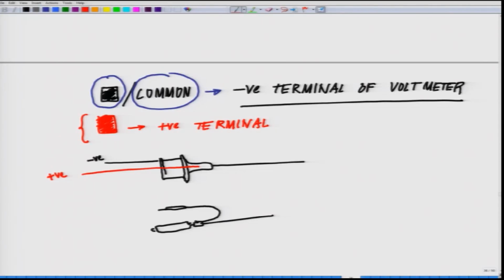Okay. Similarly, if you look at these older style ones, which you mostly see in devices imported from the US, you will observe there is an additional thin connector. So, on these pH meters, this is called the reference or negative terminal, and the pH is on the positive terminal.